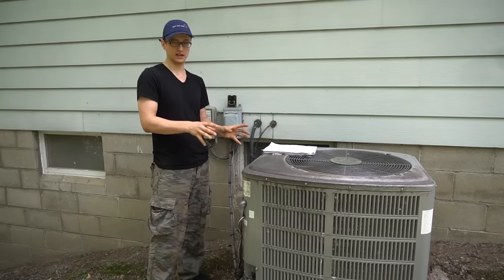That was my list of top 10 most common problems from my own orders. Let me briefly go over the honorable mentions. I had four calls where the furnace switch was accidentally turned off — usually by somebody replacing a filter — so all I had to do was flip that switch back on. I had four calls where the AC disconnect fuses were blown; you replace them, put it back in, and everything works. If it trips again, you have a bigger problem than just the fuses.